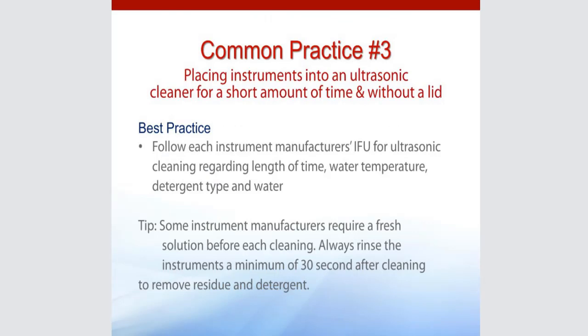And now we're looking at common practice number 3: placing instruments into an ultrasonic cleaner for a short period of time and/or without a lid, or adding instruments after a cycle has already begun. Those are all considered tribal practices, and they are not within the IFU. So you want to make sure that you're keeping your ultrasonic filled to the appropriate fill line, so the instruments are going to be adequately covered.